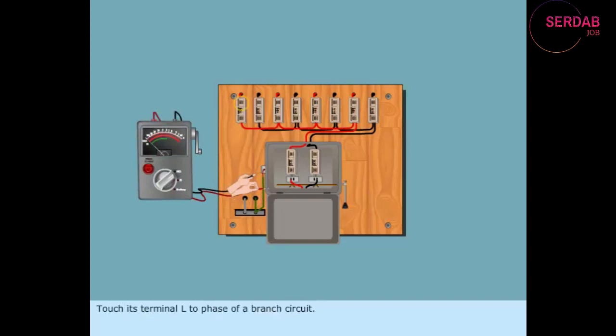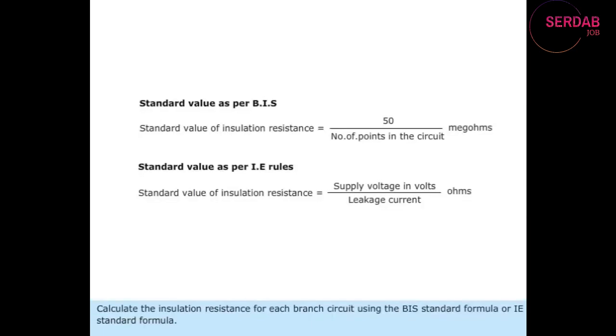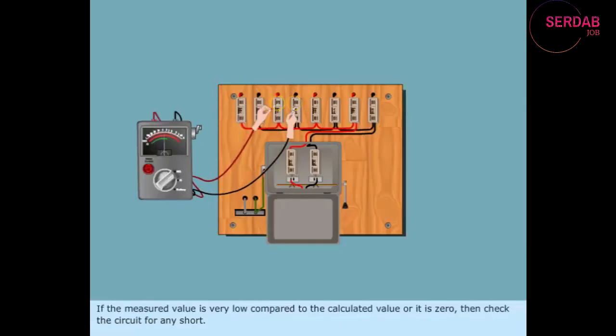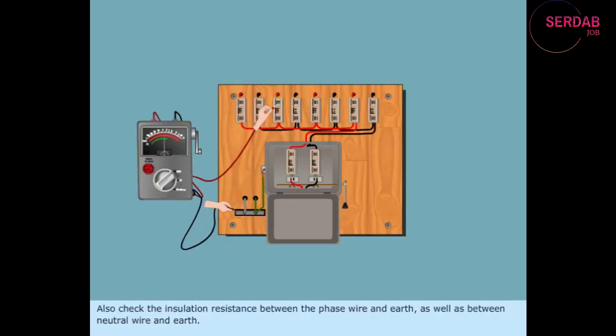Touch its terminal L to phase of a branch circuit. Touch the megger terminal E to the neutral point. Rotate the handle of the megger. Read the insulation resistance value shown by the megger. Calculate the insulation resistance for each branch circuit using the BIS standard formula or IE standard formula. If the measured value is very low compared to the calculated value or it is zero, then check the circuit for any short. Also check the insulation resistance between the phase wire and earth, as well as between neutral wire and earth.